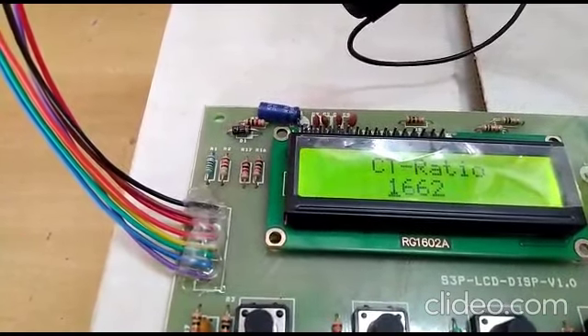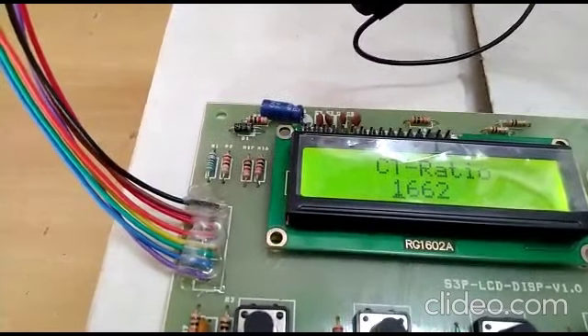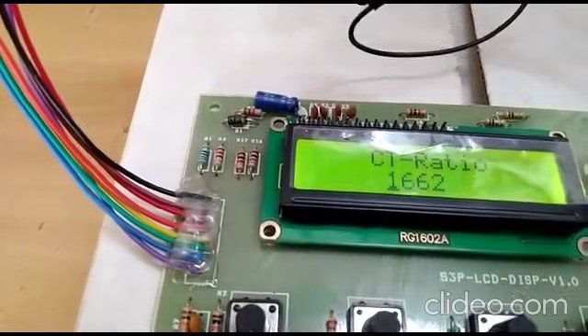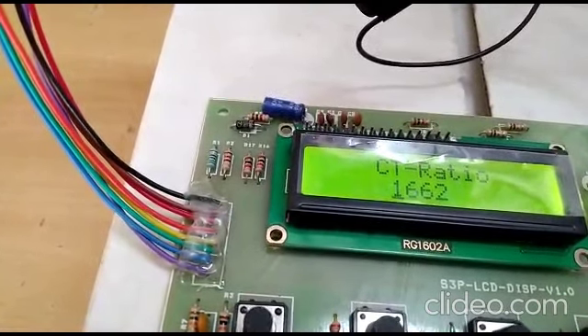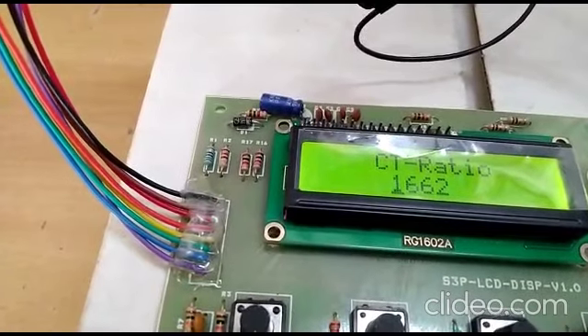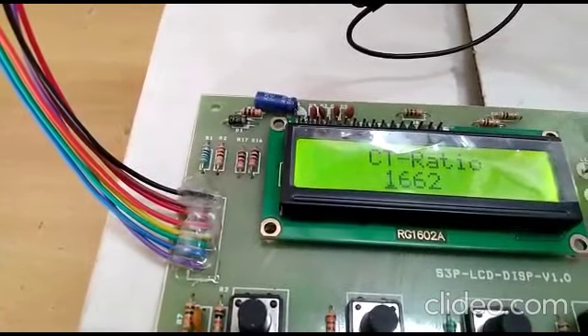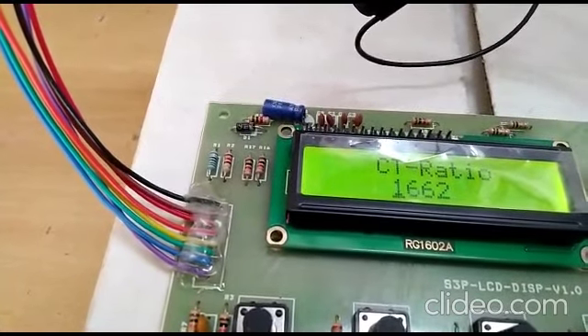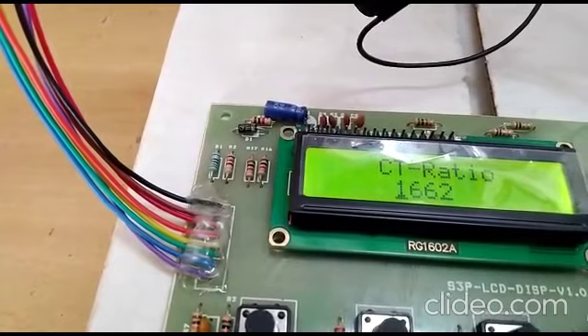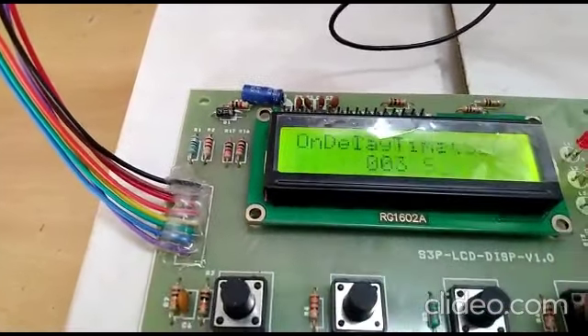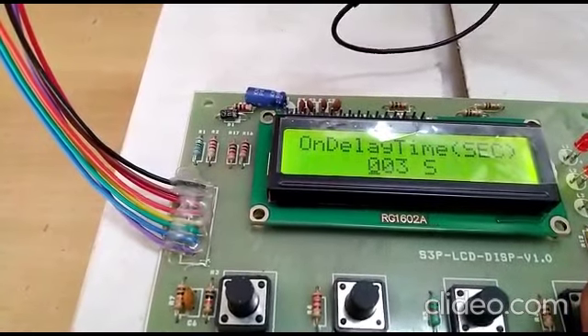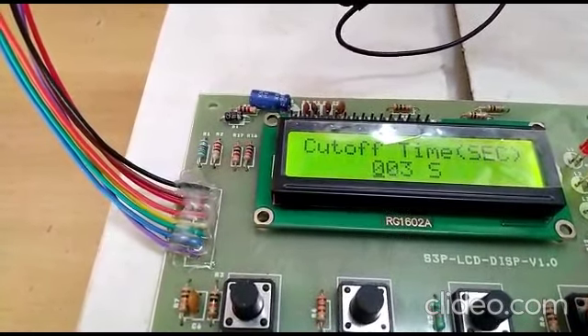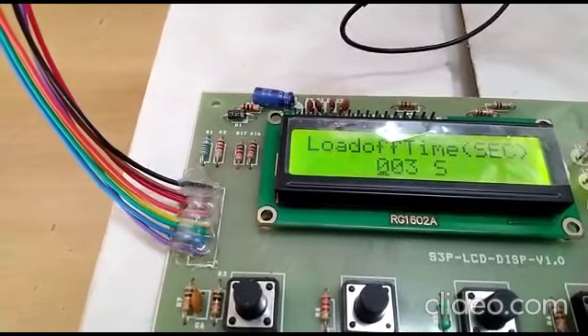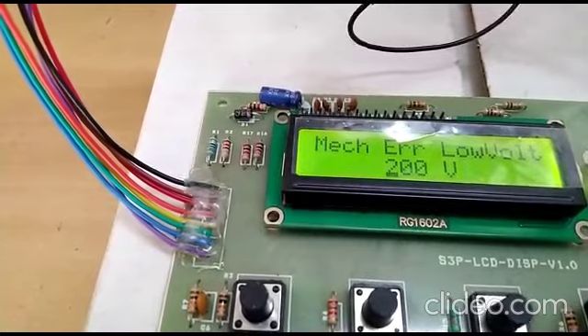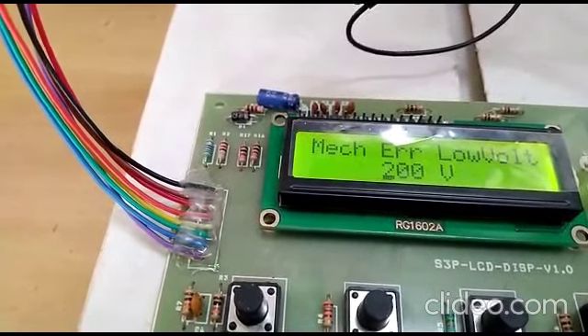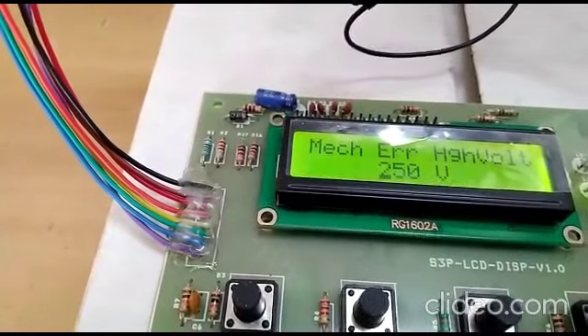CT ratio is 1662. If the current transformer coil is changed, for example if we put a 30:5 ratio coil, you should change this value. The next one, on delay time, is 3 seconds. Cutoff delay time is 3 seconds. Load off delay time is 3 seconds. The next ones are mechanical error low voltage and mechanical error high voltage.